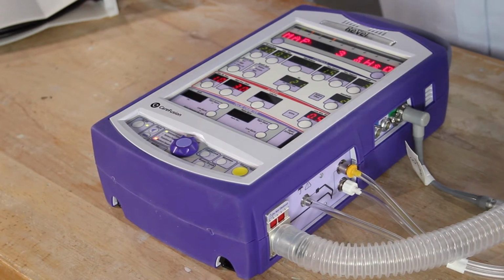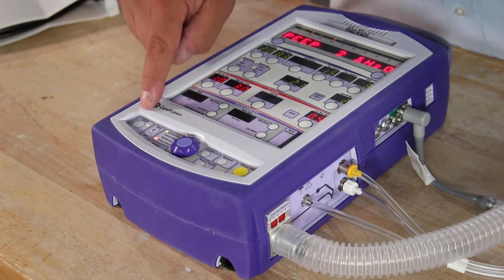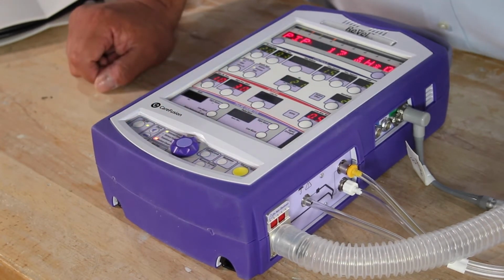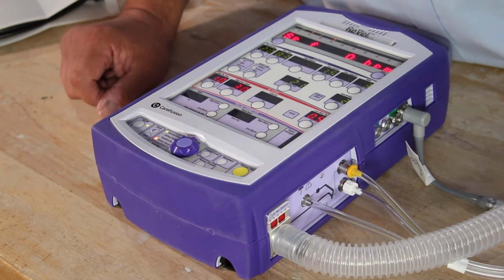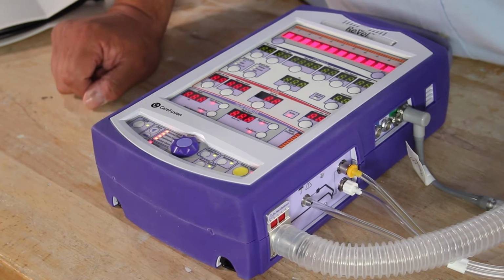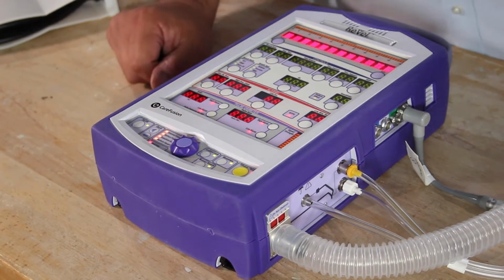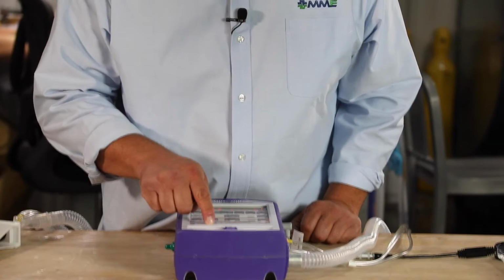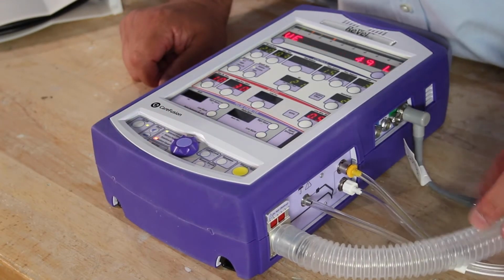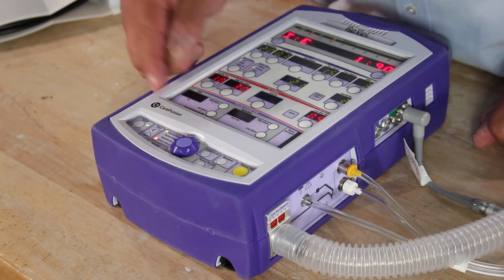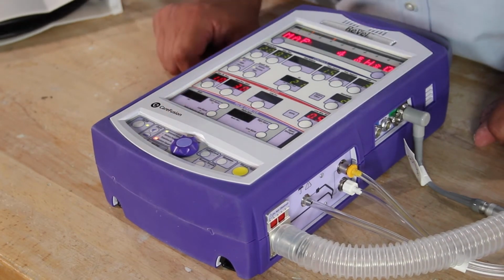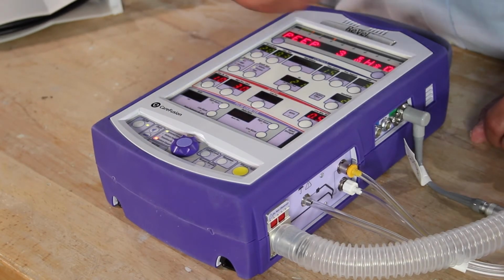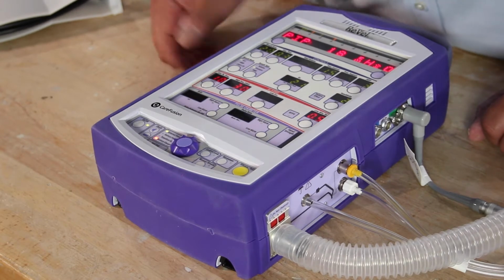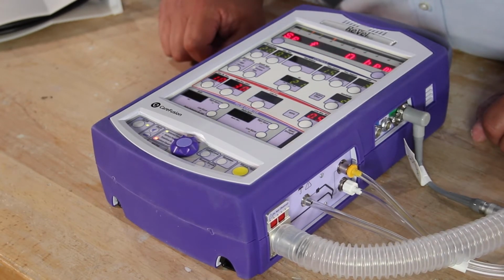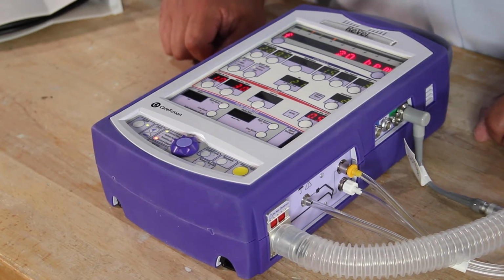All right, let's run through a couple things on the ventilator itself. All our alarms are set up right here at the lower section. So we have audible alarm, and we're checking it. Everything lit up just to make sure. On the front of the vent, it's called external power, and that's right there, simple, connects to the wall. Then we have a battery pack, which is the hot swappable battery, and then we have a transitional battery, which simply stated just allows you enough time to pop in a battery, pop out, okay? The hot swappable battery lasts 3 to 4 hours and is completely dependent on the patient's minute ventilation.